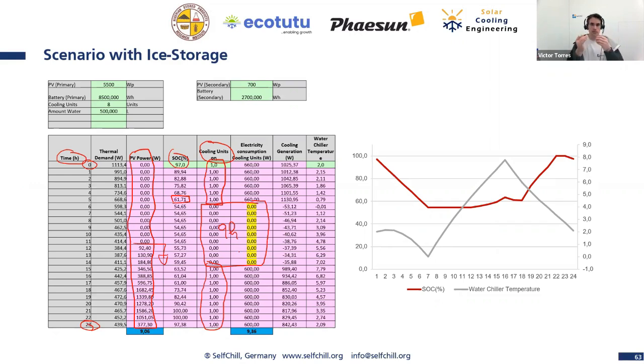There are, of course, different variations of this. But if we do it like this, that the cooling units are allowed to be stopped for 9 hours per day, yeah, at night. Then I did the calculation for the battery that we need, and I came to this value. We need 4.5 kilowatt hour batteries. We need a little bit more of PV, so not 4.2 but 5.5.